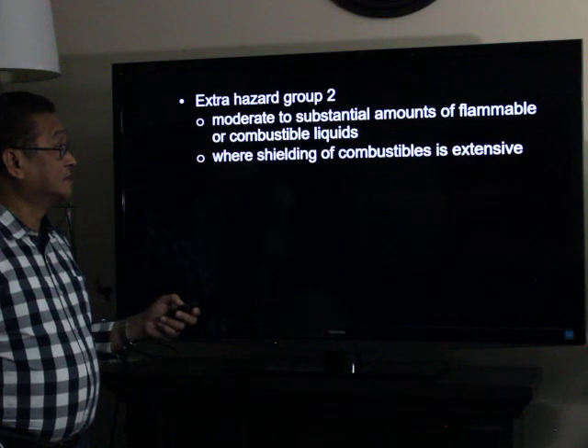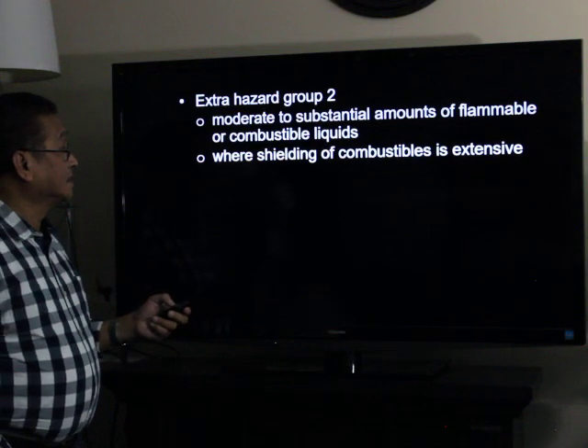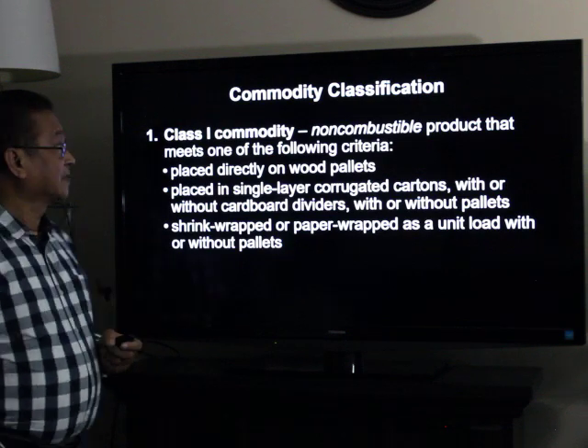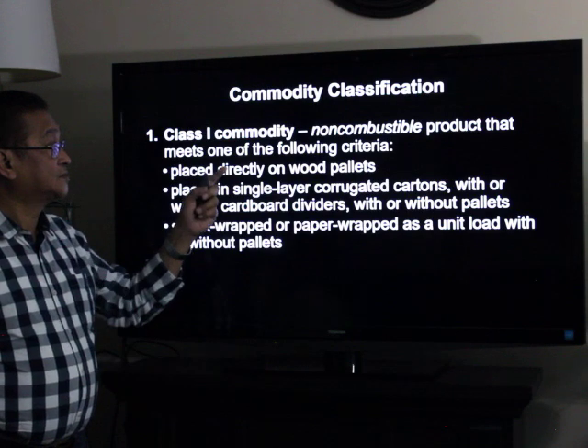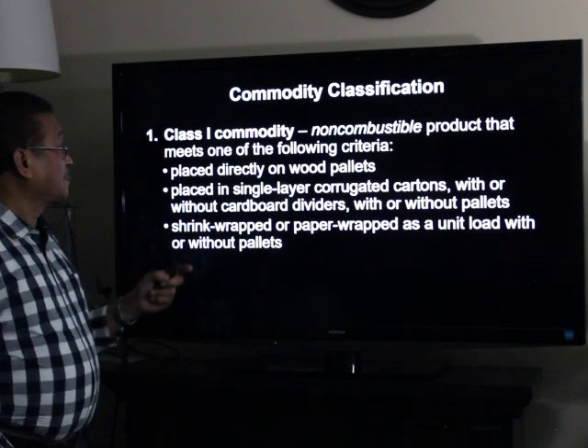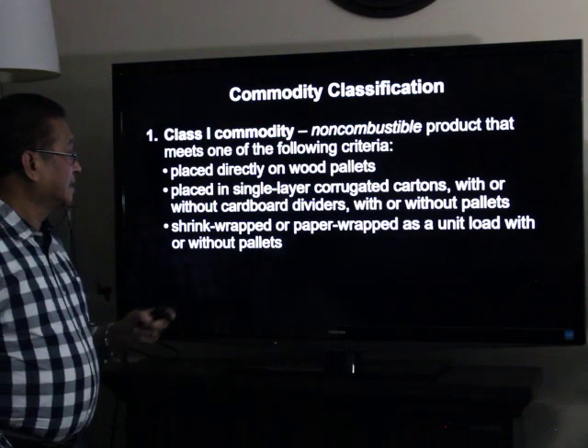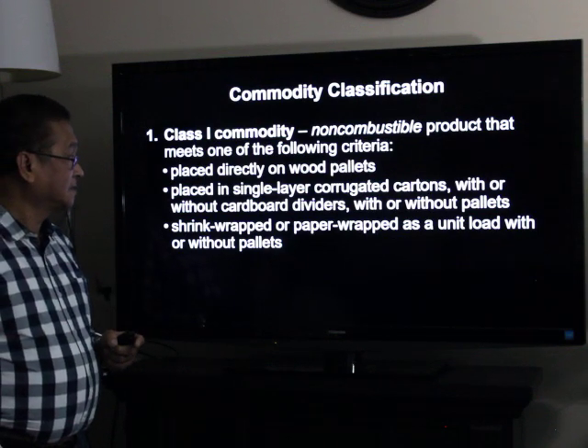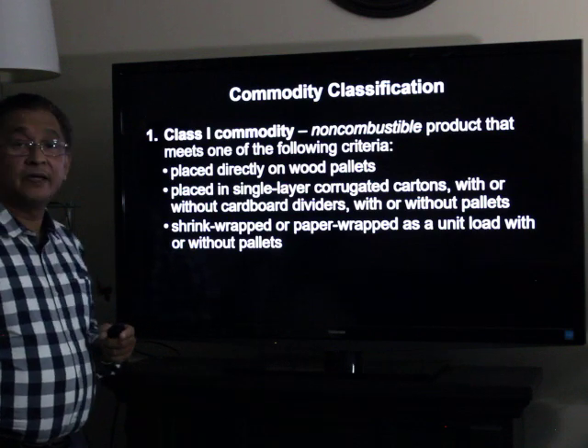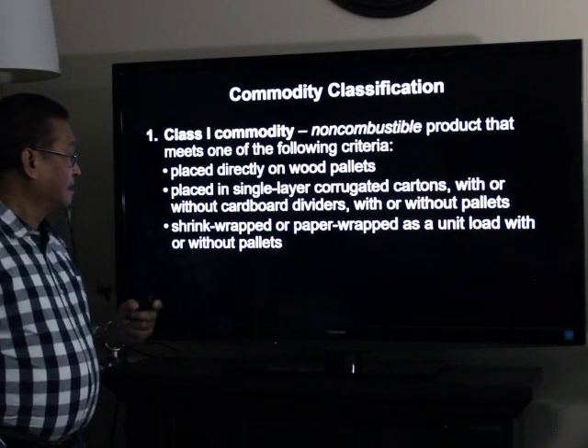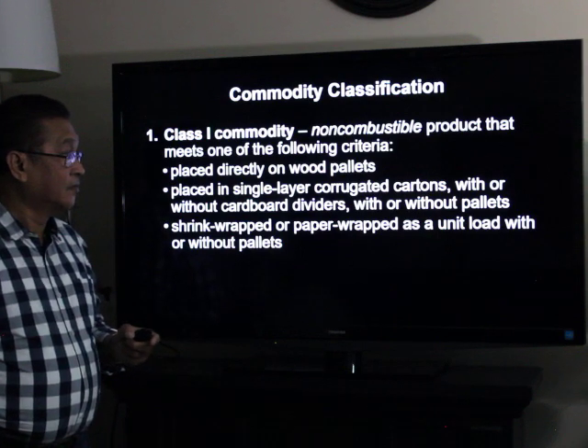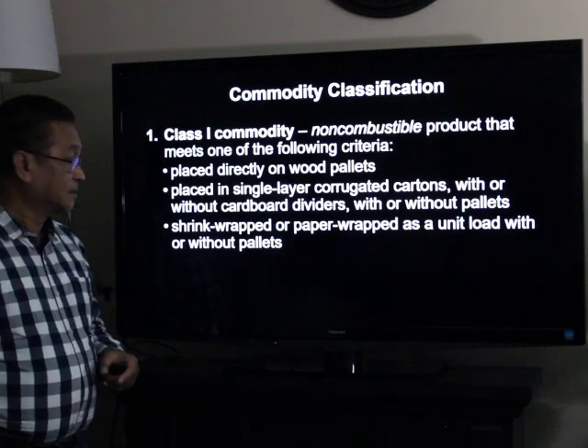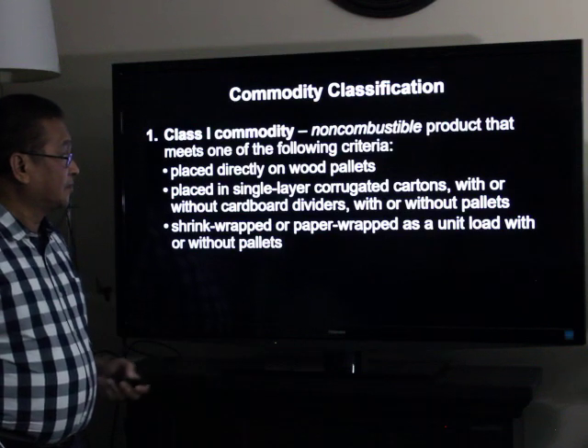For commodities, we have four classifications. Class one commodity refers to a non-combustible product that meets one of the following criteria: number one, placed on pallets; second, placed in single-layer corrugated cartons with or without cardboard separators, with or without pallets; or shrink-wrap or paper-wrap as a unit load with or without pallets.